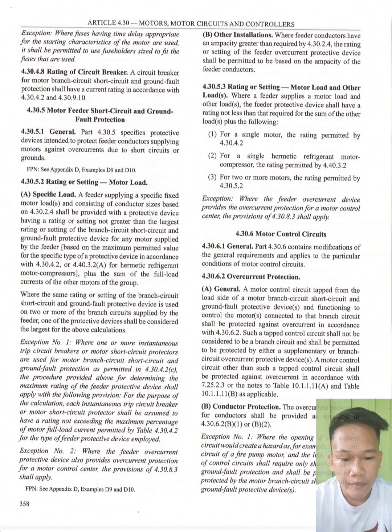The procedure provided above for determining the maximum rating of the feeder protective device shall apply with the following provisions. For the purpose of the calculation, each instantaneous trip circuit breaker or motor short circuit protector shall be assumed to have a rating not exceeding the maximum percentage of motor full load current permitted by Table 4.30.4.2, which you may remember, for the type of feeder protective device employed. The second exception is where the feeder overcurrent protective device also provides overcurrent protection for a motor control center. The provision of 4.30.8.3 shall apply.